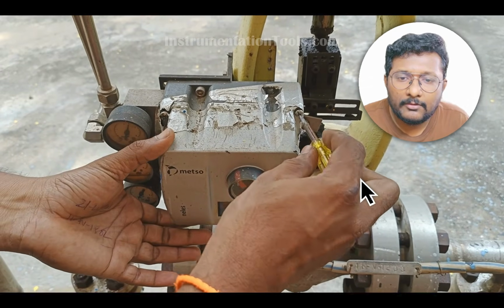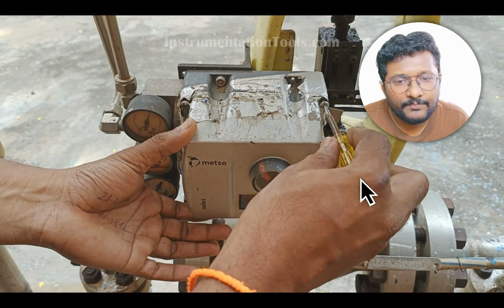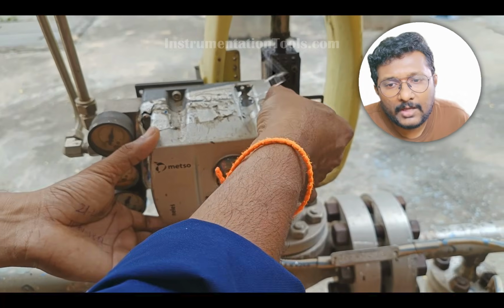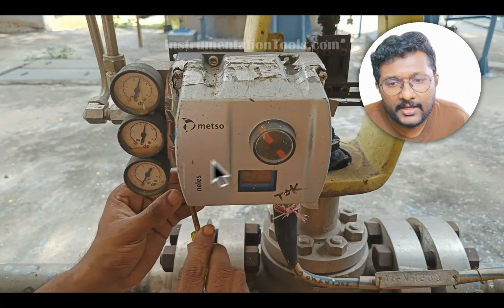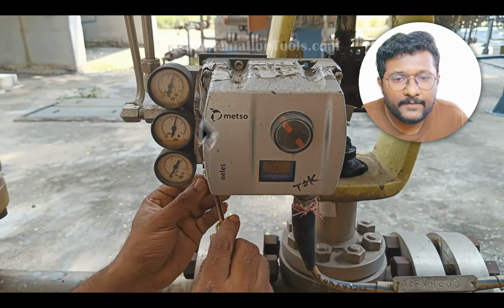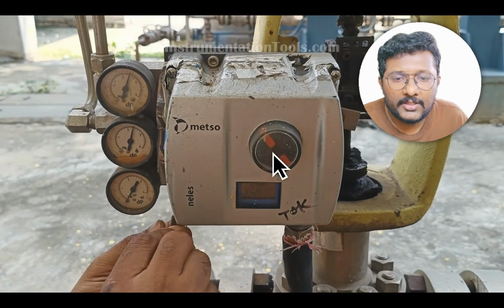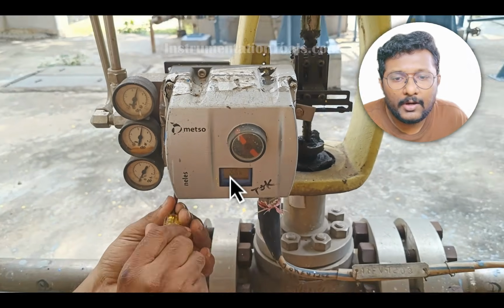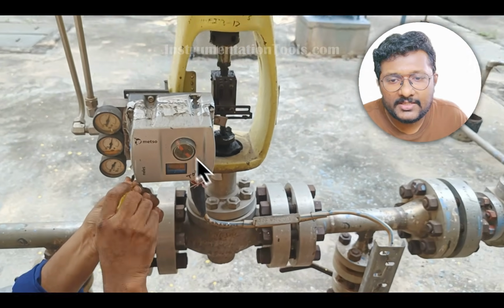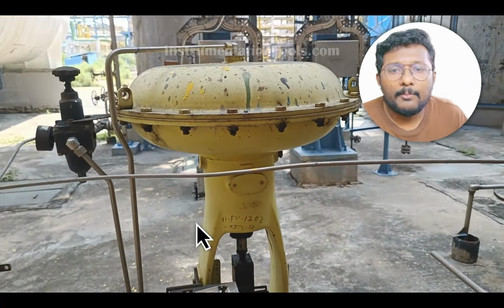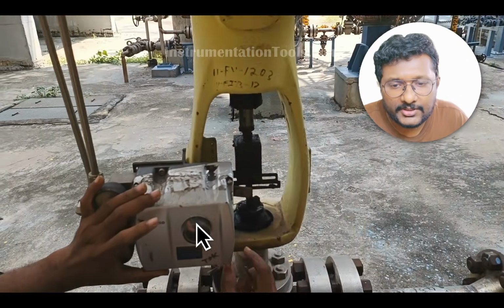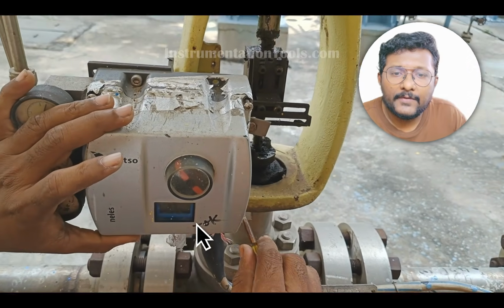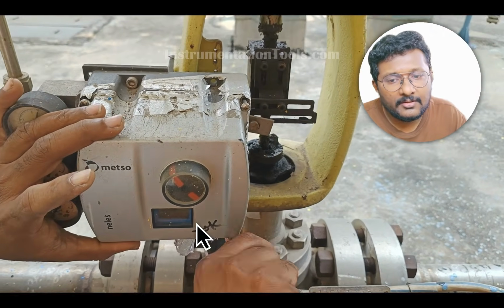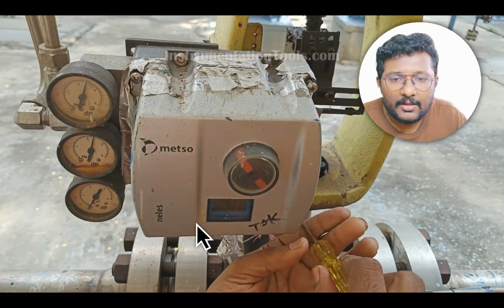using valve positioner display. Now first I will remove the 4 screws here and then I will remove the front cover so that I can access the valve positioner display. This is a small display mounted on the valve positioner. You can do the configuration, you can do the calibration from this display.